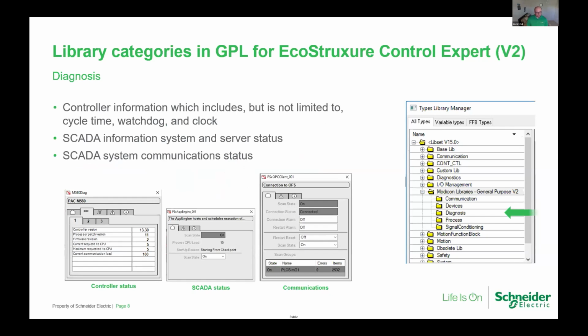When we go into the diagnosis, we have different faceplate templates that can grab that information and display it in something more user digestible. Rather than having just a screen set up to intake those diagnostic informations, we have these faceplate templates. So if you want to diagnose or take a look at what the controller's doing, maybe the controller version, processor information, scan time, watchdog information, we have a faceplate template here that's dedicated to the Modicon M580 platform.